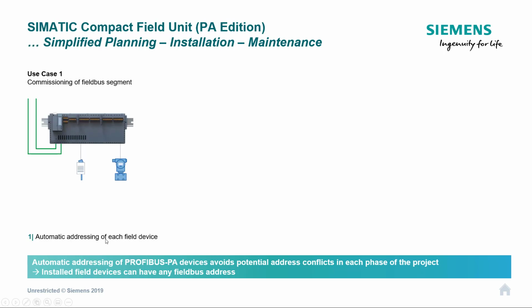So the first thing that it does is it automatically addresses the instruments. So what we don't have now, we don't have a Profibus PA network, we just have individual Profibus PA connections that can go up to 120 meters for each device. So one device on each connection, 8 Profibus PA devices on one Compact Field Unit. When you plug your Profibus PA device into connection 1, it sets the address to 20, and connection 8, it sets the address to 27.